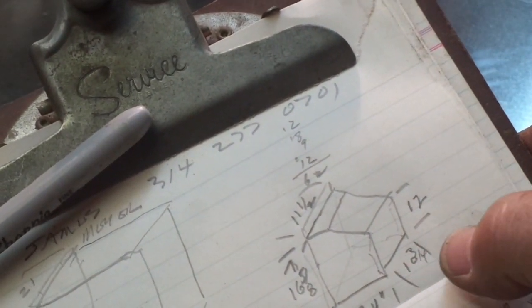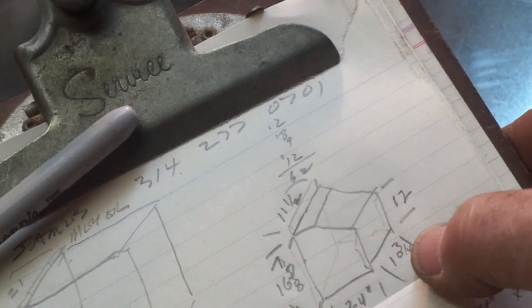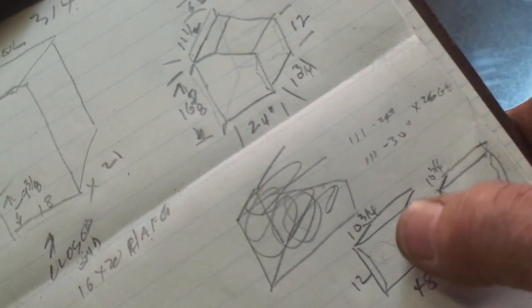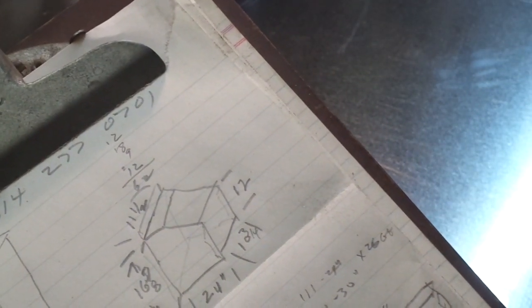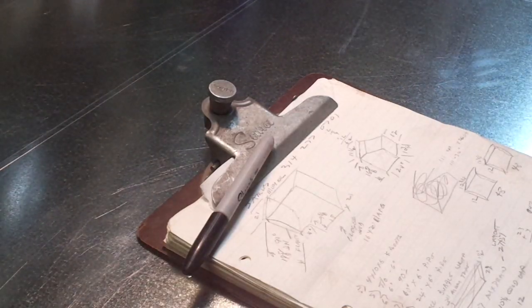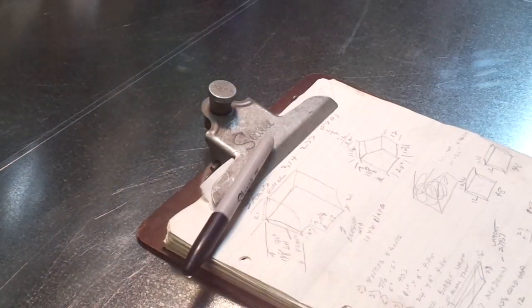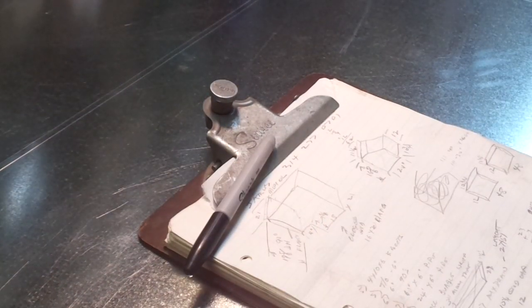Was going to make it 10 inches, but by converting that to 10 3/4, that allows the trunk lines down here, which are going to be 12 by 10 3/4 now, it allows me to utilize the maximum amount of the material of a 24-inch sheet of metal without having to make any cuts, because 12 plus 10 3/4 plus one inch for the Pittsburgh plus 1/4 for the 90 degree angle that goes into the Pittsburgh totals 24 inches. So I'm saving a set of cuts across the width of the metal, or the length of the metal.